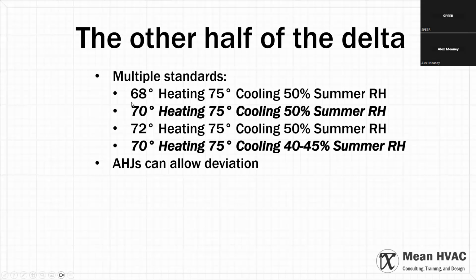They don't do anything to the cooling. The ACCA's recommended design, they call them default design conditions. And they're very particular about language over there. So I believe that's important to note. It's not required like it is for cooling. It's default. And it's 70 degrees for heating, 75 degrees for cooling with a 50% target summer relative humidity. The National Energy Code will throw out 72 degrees just to be different. I don't know why, it's very annoying. But they have a 72 degree for heating, 75 for cooling, 50% RH for some of their standards. 70 heating, 75 cooling, 50% relative humidity is certainly a solid standard to use for the vast majority of Texas.